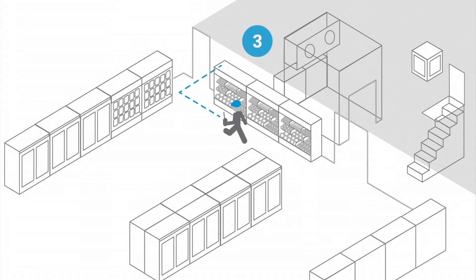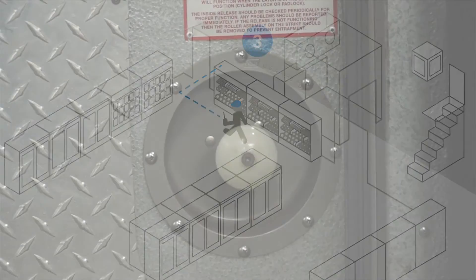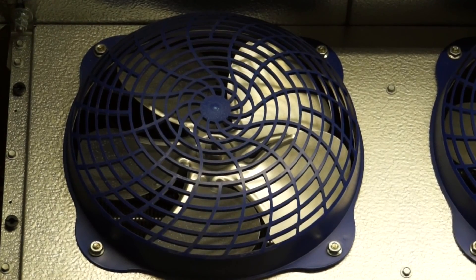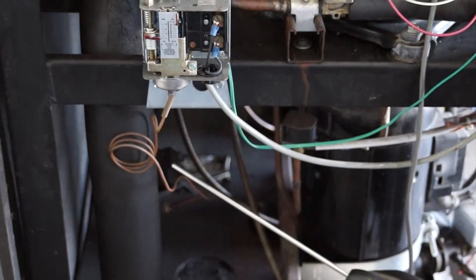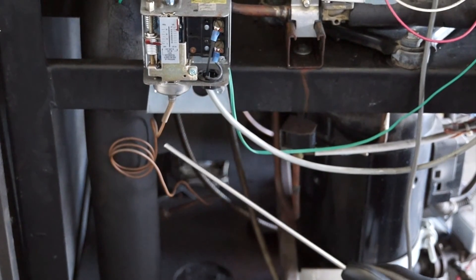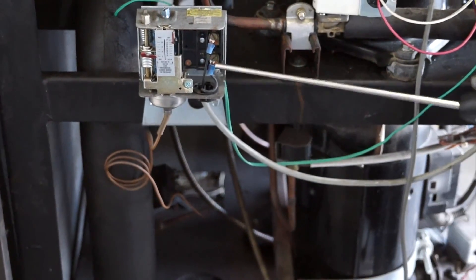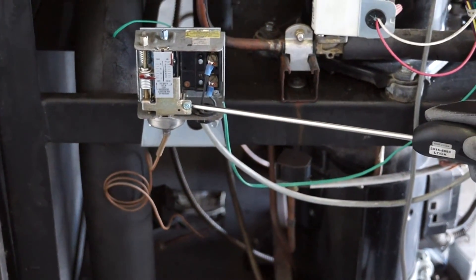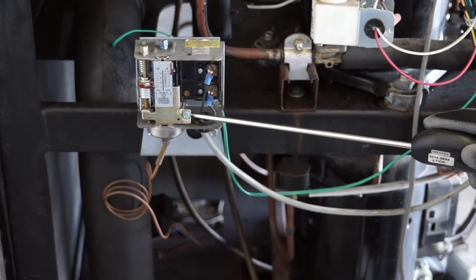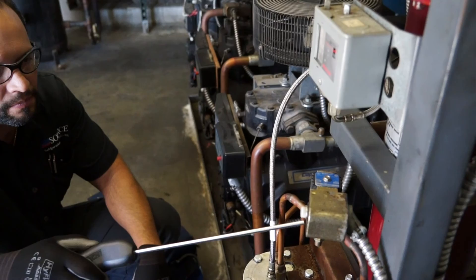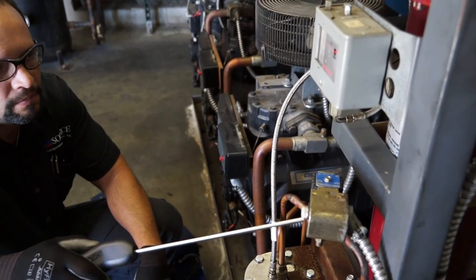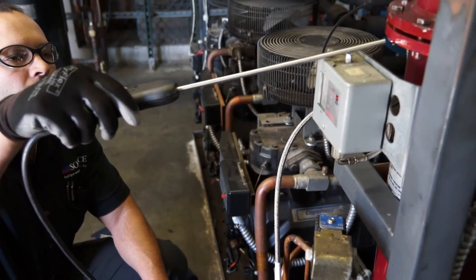Then return to the machine room. A large leak will indicate as soon as you open the door. Be sure to minimize drafts by shutting off fans or other air movement devices. Slowly sweep the detector around the equipment. Use caution when checking for leaks near exposed electrical wiring. Since refrigerant is heavier than air, it will tend to flow downward — always position the probe tip below the suspected leak.